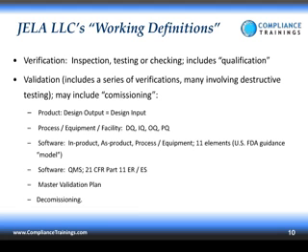Okay, well, we'll talk about each one of these elements, but you notice here, design validation is basically to ensure the device conforms to user needs and intended uses. I'll show a chart later on from the FDA that justifies my definition, but some companies do have a parallel. They have a validation of product and then they have a verification of product, each tied to the elements described in 820.30. So verification they would define as proving that the design output meets the design input, and validation proves that the user needs have been met by the resulting product.